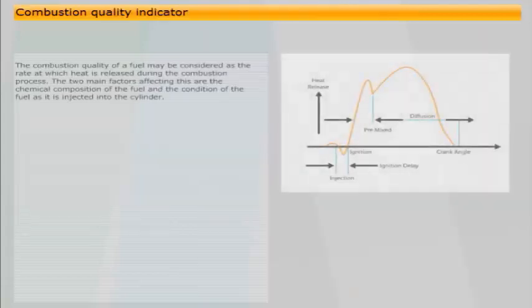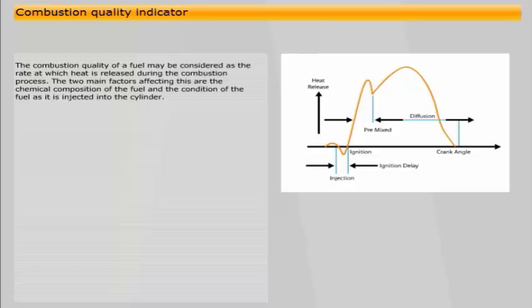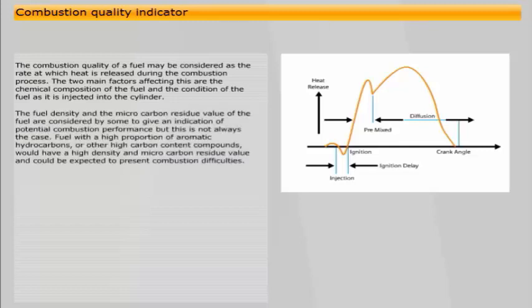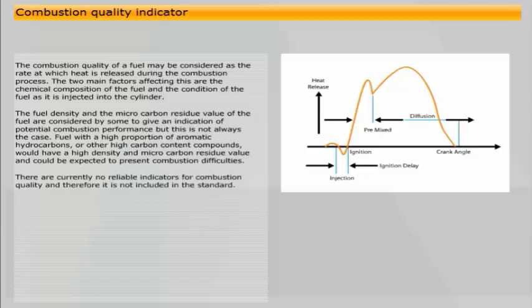The combustion quality of a fuel may be considered as the rate at which heat is released during the combustion process. The two main factors affecting this are the chemical composition of the fuel and the condition of the fuel as it is injected into the cylinder. The fuel density and the microcarbon residue value of the fuel are considered by some to give an indication of potential combustion performance, but this is not always the case. Fuel with a high proportion of aromatic hydrocarbons or other high carbon content compounds would have a high density and microcarbon residue value, and could be expected to present combustion difficulties. There are currently no reliable indicators for combustion quality, and therefore it is not included in the standard.